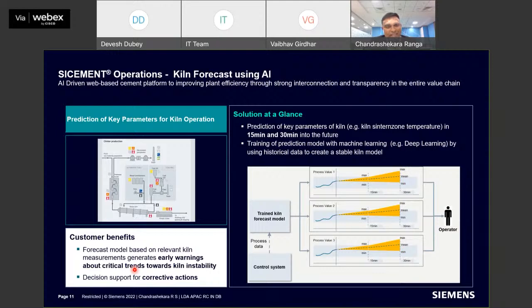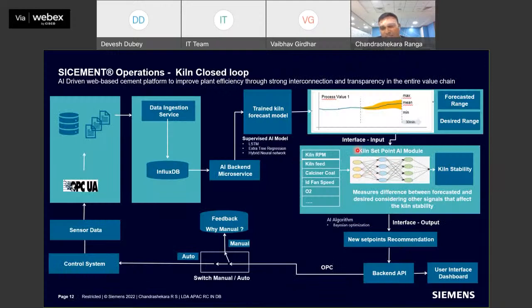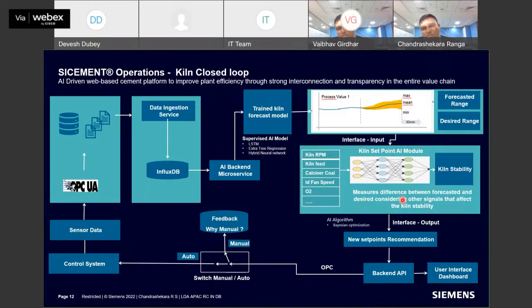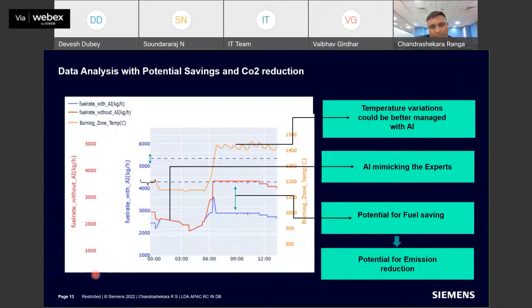This was the story till last year, but we did not stop there. We went ahead to the next stage, called set point generation. You can see that from the control system, we got into the forecast till last year, but this year we have come up with a new enhancement called set point generation, which automatically sets the set points that are needed and sends them to the control system. This means the whole kiln operation, as a control loop, can run without any human intervention in a very optimal condition. This has been tested and is working at 2 pilot customers for more than 6 months now, and it's yielding very promising results.